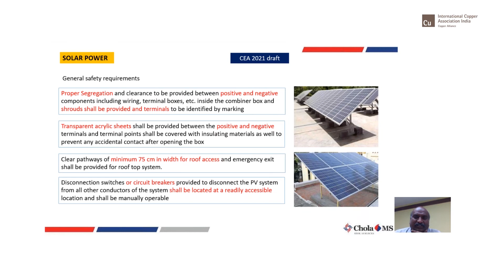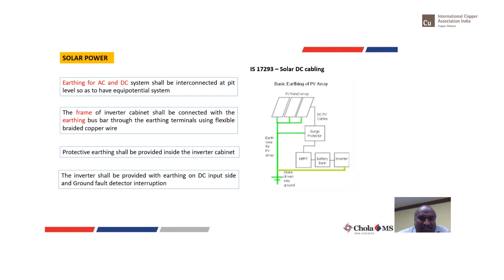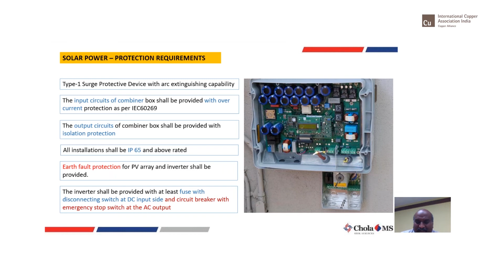There is also an IS standard which has come up, IS 17293, which gives more detail on solar DC cabling. They also talk about earthing on the AC side and DC side. All the steel metal frames should be earthed. Protective earthing shall be provided for inverters, boxes, all those things. It also talks about surge arresters to be installed. The output circuit of the combiner box shall be provided with isolation protection and earth fault protection. As in any normal electrical circuit, isolators and the necessary surge protection devices have to go in as part of the protection mechanism for the solar systems that you have installed on your rooftops, at your facility, or at any location where you are currently working.